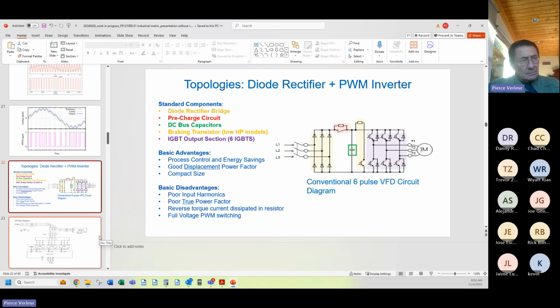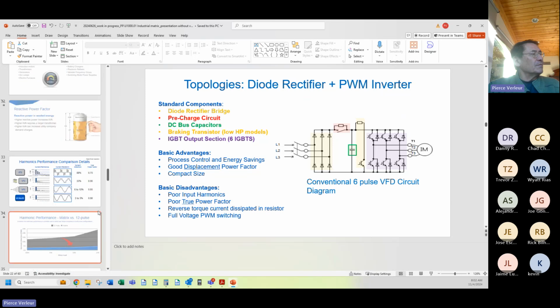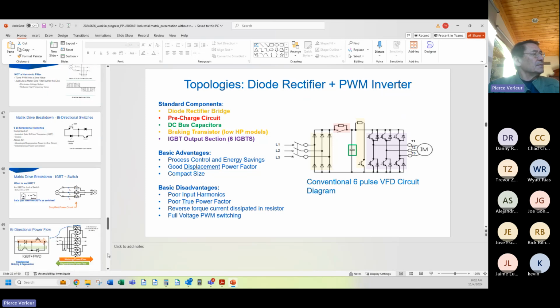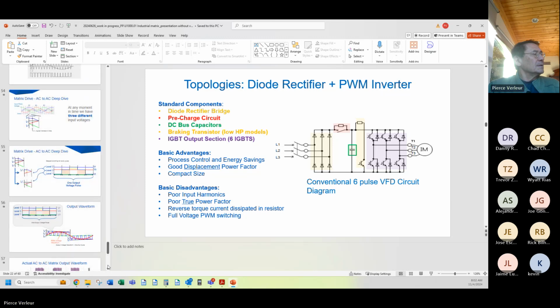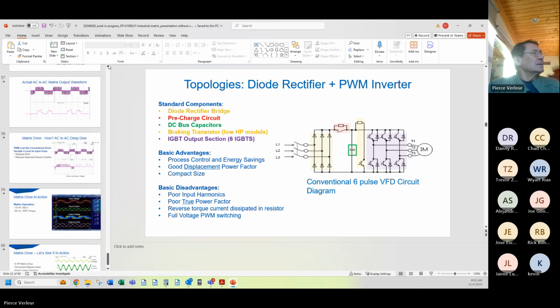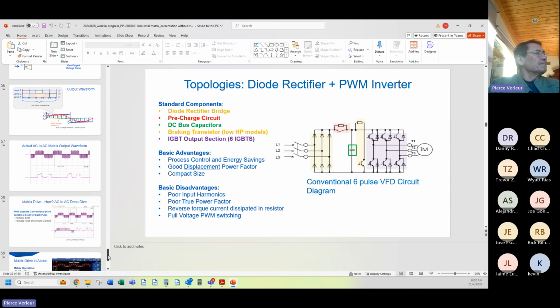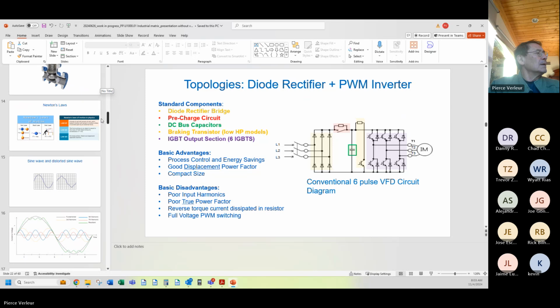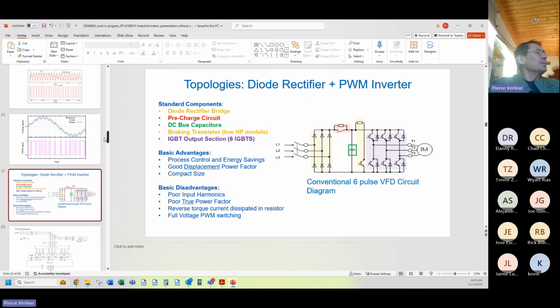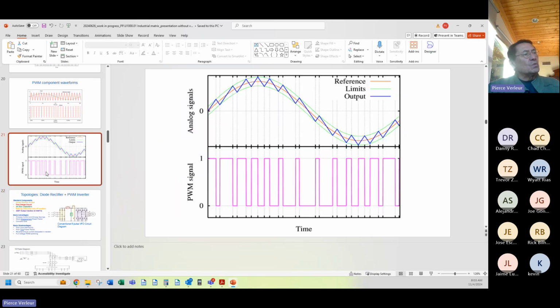Now, the last subject I want to talk about, which is a significant advantage to Matrix over what they call traditional VFDs. Another way of talking about it is a DC bus-based pulse width modulated output VFD. Let me see if I can show you a picture of pulse width modulation. That's not it. Hang on. There we go. This is pulse width modulated output of a VFD, whether it's a diode front end VFD, whether it's an active front end VFD, but it's not matrix.